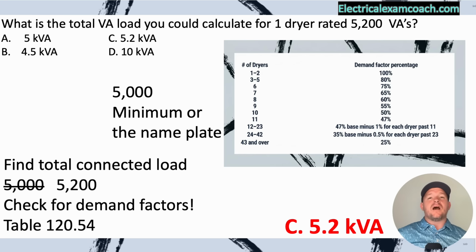Great job. I'm walking you through this template of how to do all load calculations NEC-wide. Step 1, find the total connected load. Step 2, check for demand factors. Even if you know there's not a demand factor, I still will always go check and just be thorough to make sure that I didn't miss something. When someone's failed the calculations test over and over and over, I go back through them with them over a few key questions, and you'll find that they're just missing the little details, thinking that they know the answer instead of checking in the book.